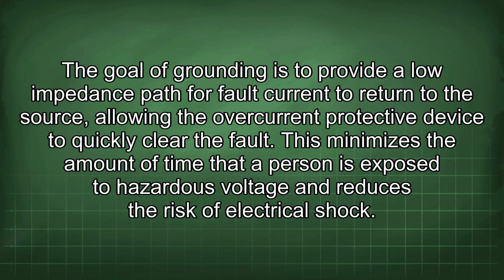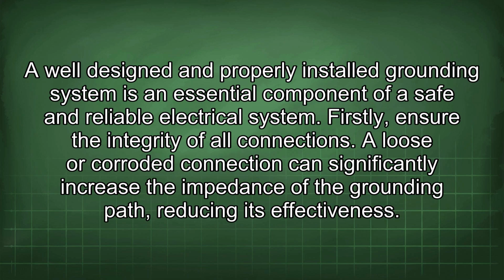The goal of grounding is to provide a low impedance path for fault current to return to the source, allowing the overcurrent protective device to quickly clear the fault. This minimizes the amount of time that a person is exposed to hazardous voltage and reduces the risk of electrical shock. A well-designed and properly installed grounding system is an essential component of a safe and reliable electrical system. Firstly, ensure the integrity of all connections. A loose or corroded connection can significantly increase the impedance of the grounding path, reducing its effectiveness.